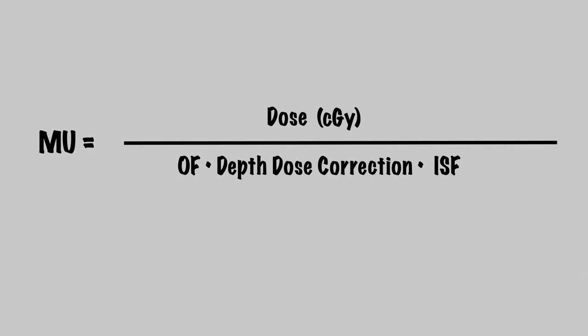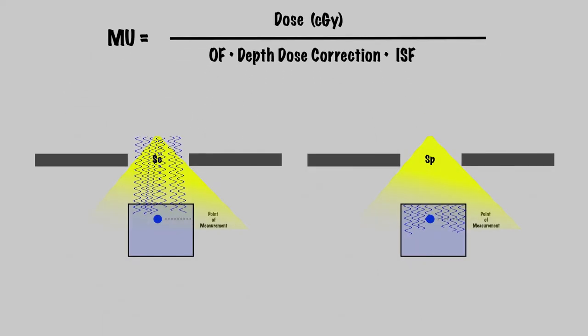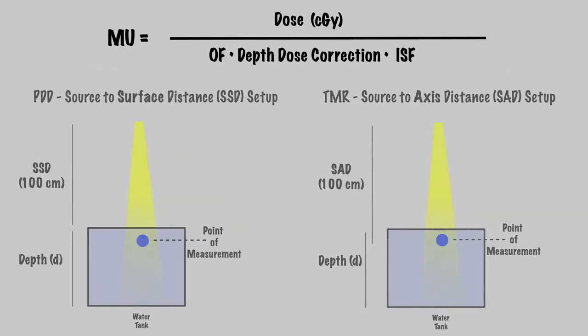The collimator scatter, or S sub C, and phantom scatter, S sub P, together are termed the output factor. The output factor will account for the change in dose rate due to field size. The depth dose correction factors of PDD and TMR values will be needed for the SSD and SAD setups respectively. Physicists measure each of these values - the output factor, the PDD, and the TMR - during commissioning of each LINAC and generate lookup tables, which are used to perform our MU calculations.